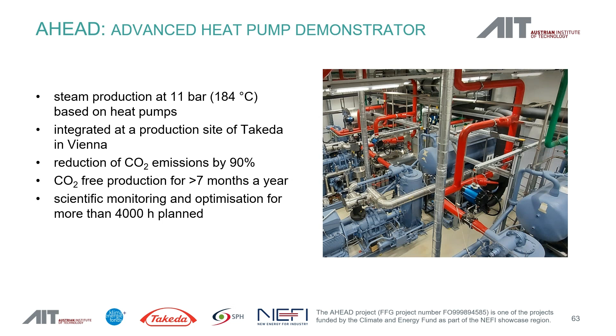And here you see how this system looks in theory and what we are going to build in the future. In blue on the left, we have the existing system. They have a central chiller unit where they produce cold utilities, or cold water, for the production at a temperature of 6 degrees. And the central chiller has waste heat, so it was equipped with a heat pump. That heat pump is an ammonia heat pump. It produces water for heating purposes at 70 degrees. And we use this water at 70 as the heat source for the AHEAD system, which is a combination of a steam generating heat pump. This heat pump is provided by SPH, Sustainable Process Heat, and they will use butane as a refrigerant.